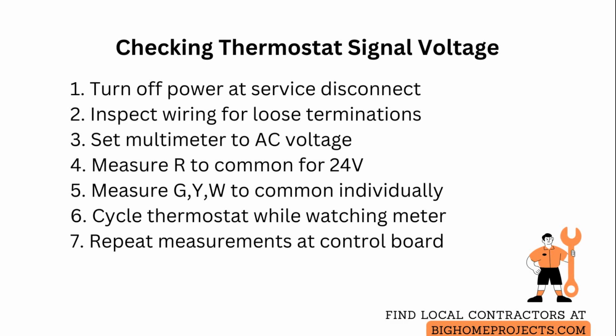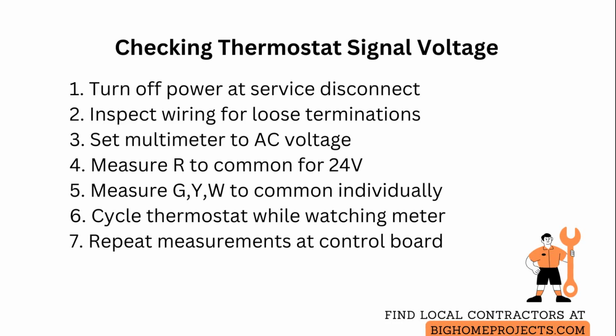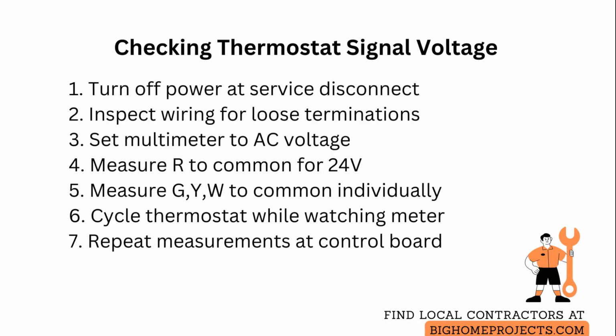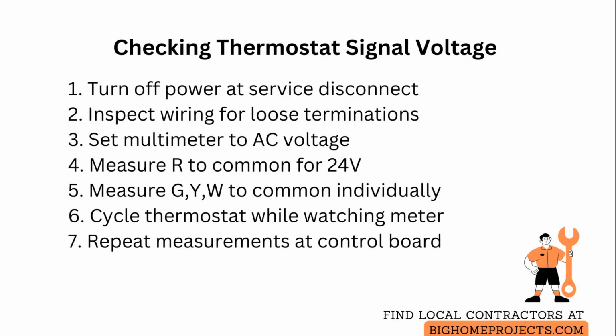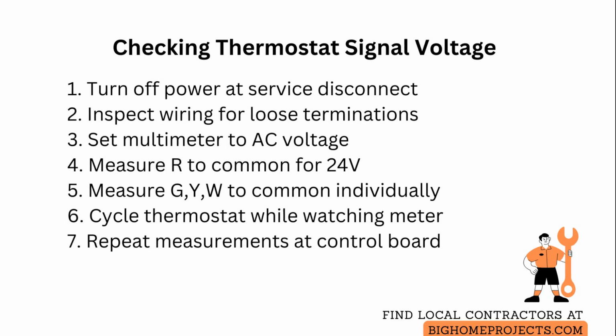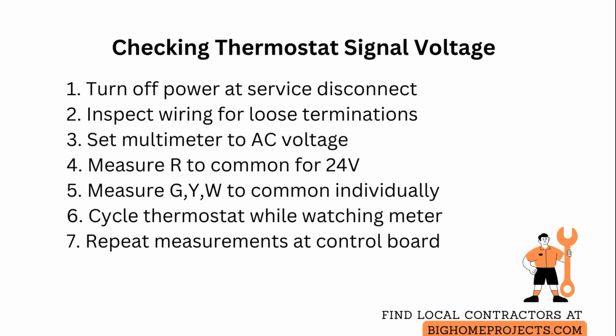If a terminal reads intermittently, cycle the thermostat function while watching the meter to see if the voltage appears only during the call, which indicates correct signaling. For accuracy, repeat the same measurements at the control board terminals and compare values. A significant difference means a wiring issue, voltage drop, or a failed transformer.